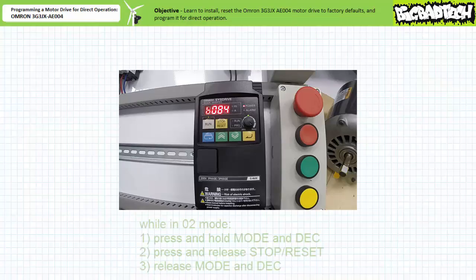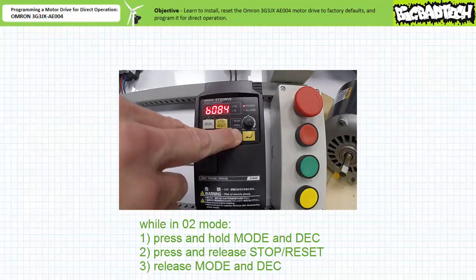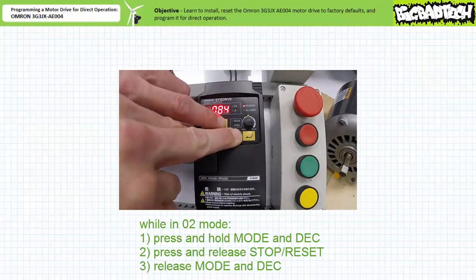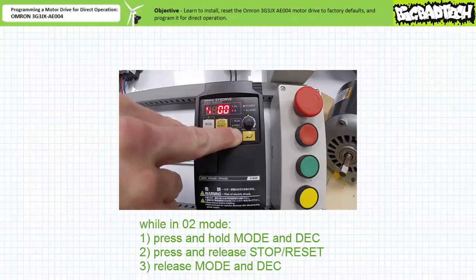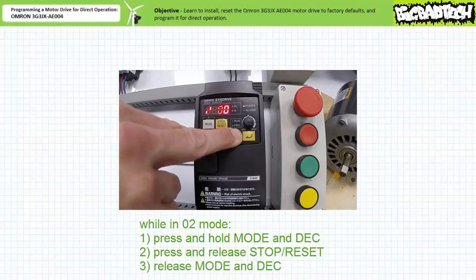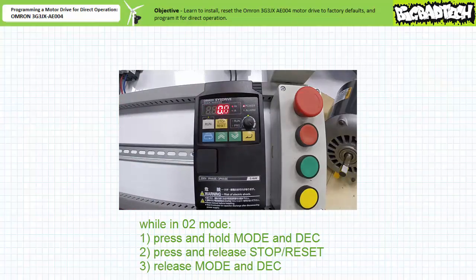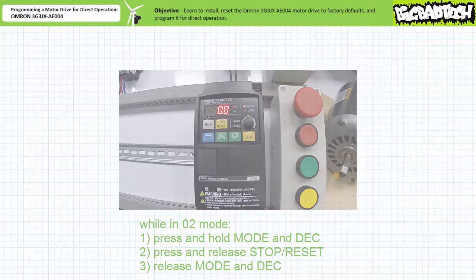To reset this drive to factory defaults and clear it, one needs to press and hold both mode and decrement keys. Then one presses stop/reset. The display kind of wigs out. Release stop/reset first, then release the simultaneously held mode and decrement keys. If you've been successful in resetting and clearing the drive, you'll be returned to the initial default D001 parameter.